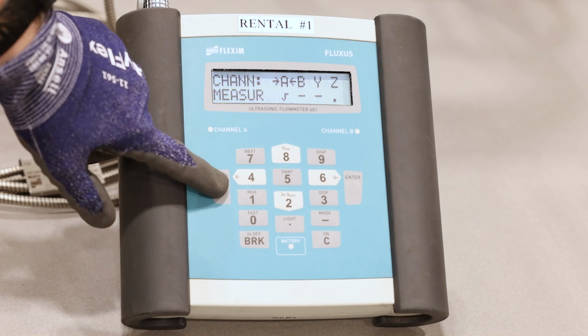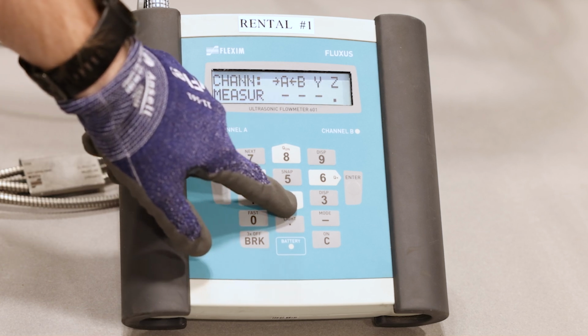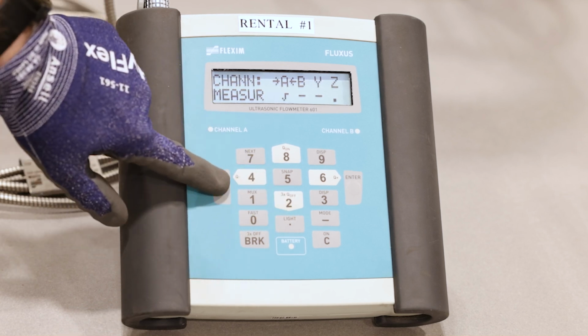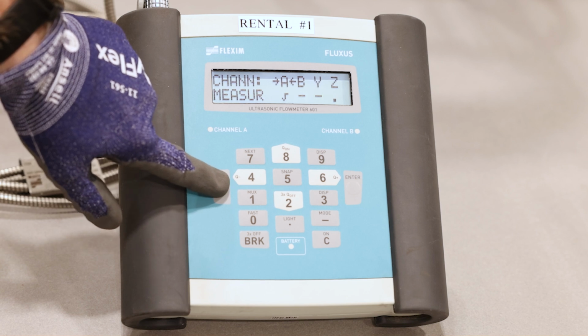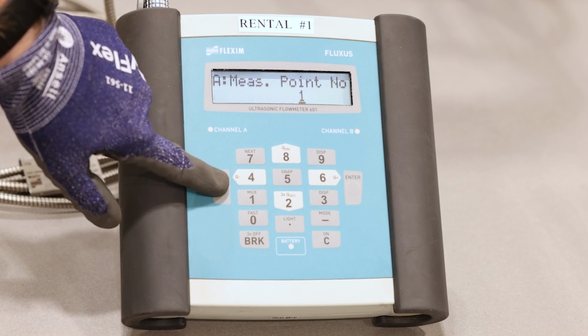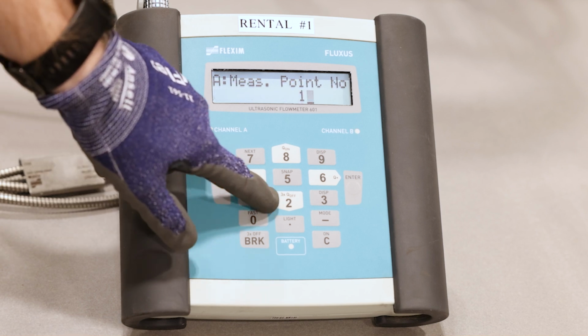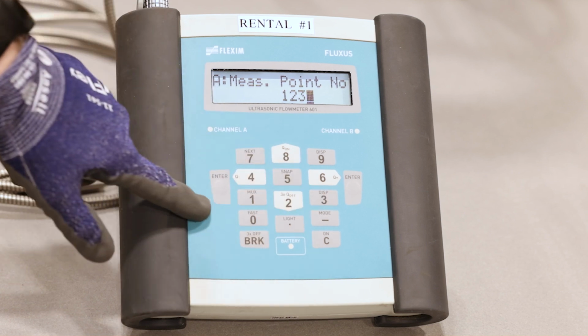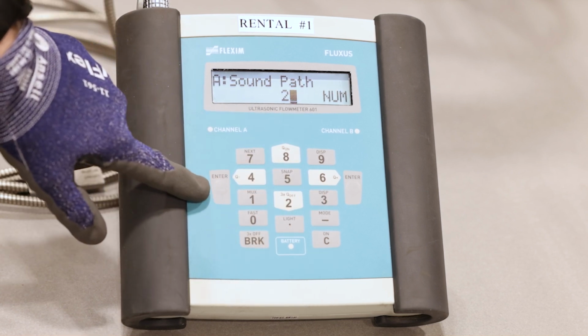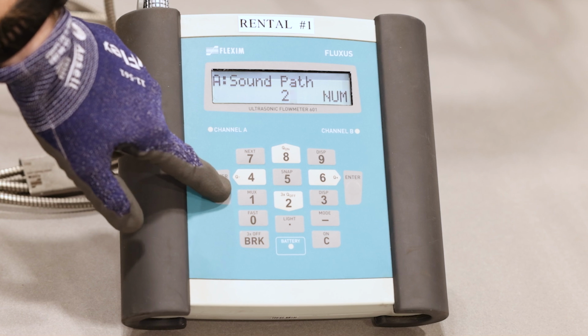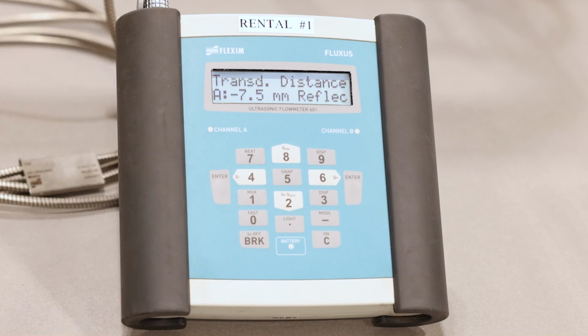This screen will show you what channels are enabled. Make sure channel A is enabled by scrolling up and down on the channel to see a check mark below. You can label the measuring point as 1, 2, 3 for this. We will be doing a 2 sound path for this installation. The optimal transducer spacing is calculated by this screen. This will be the calculated spacing we want to install the transducers at.